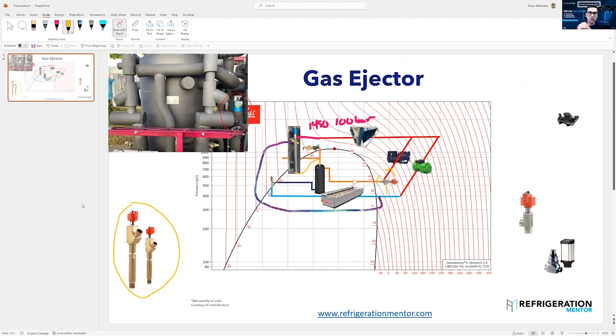They do the same thing. Instead of sending that medium temp suction gas to the medium temp compressors, it's taking it back, putting it into the flash tank. From the flash tank, it's going to the parallel compressor instead of the medium temp compressor.